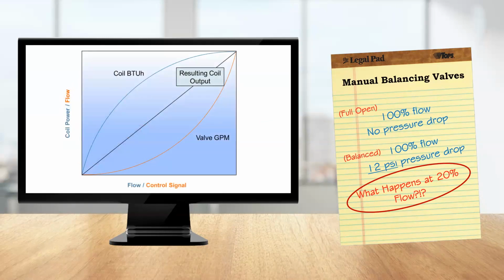But why did we choose 20% flow rate for this example? Isn't that a pretty low flow rate? Actually, it's not. Remember from our look at the coil curve earlier, 20% flow through a water coil will produce about 50% of the heat transfer, as shown here. This represents roughly a 50% control command to the valve.